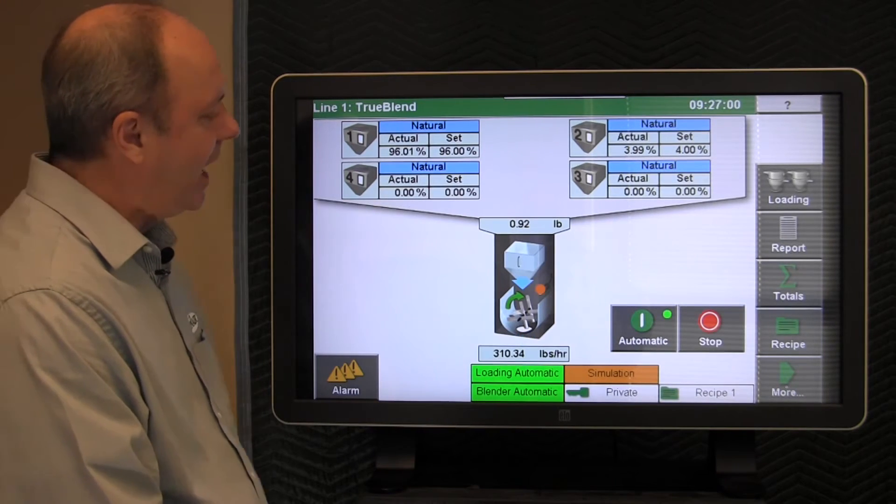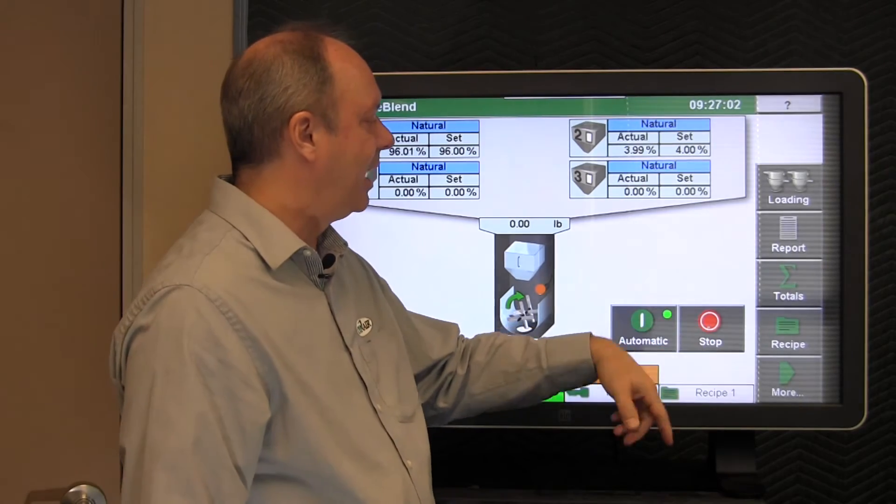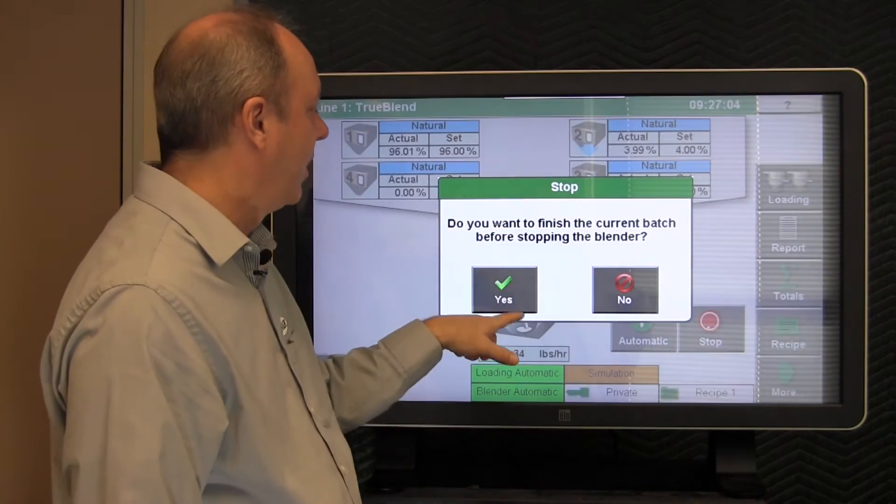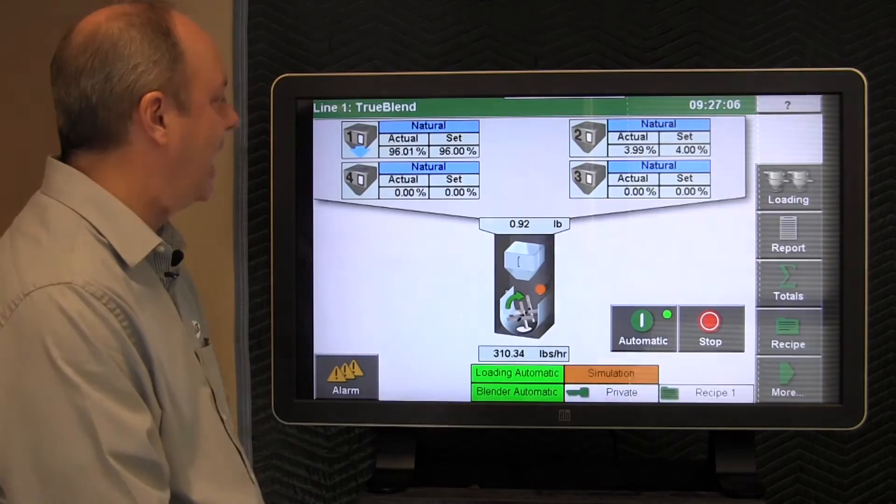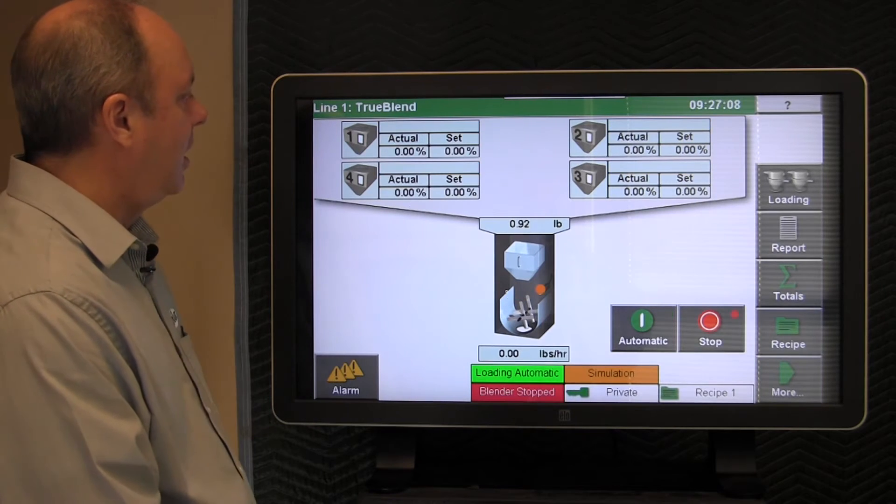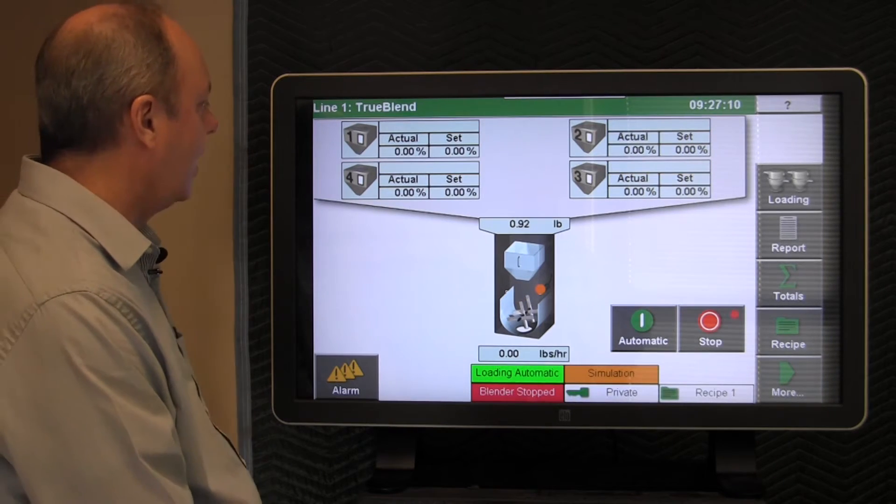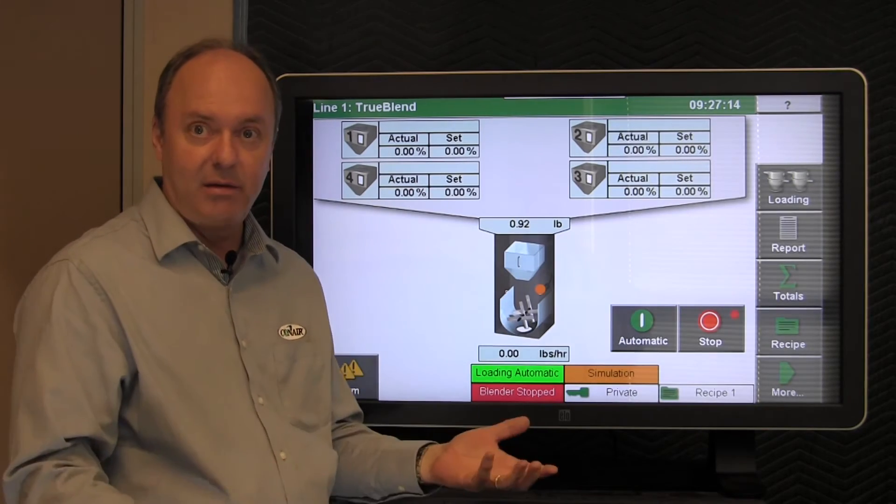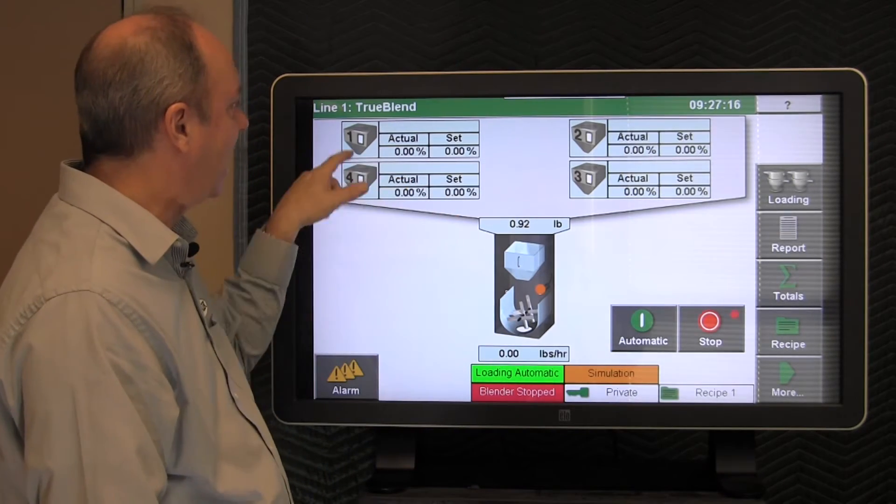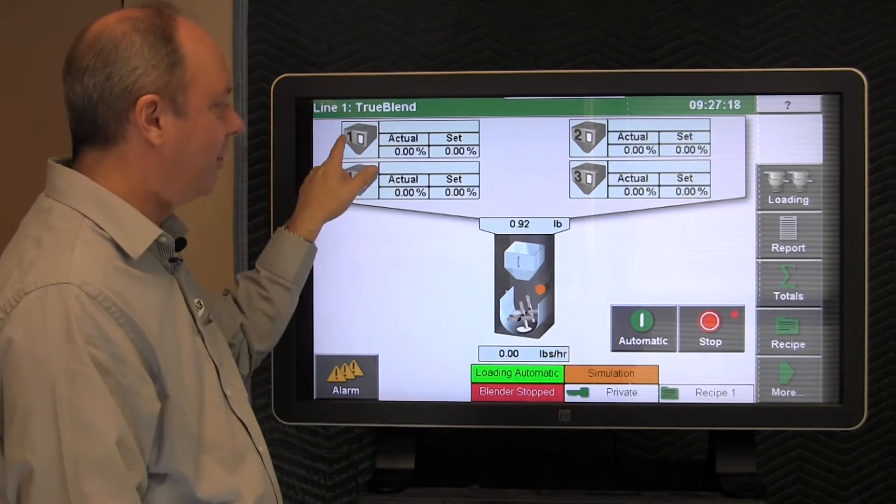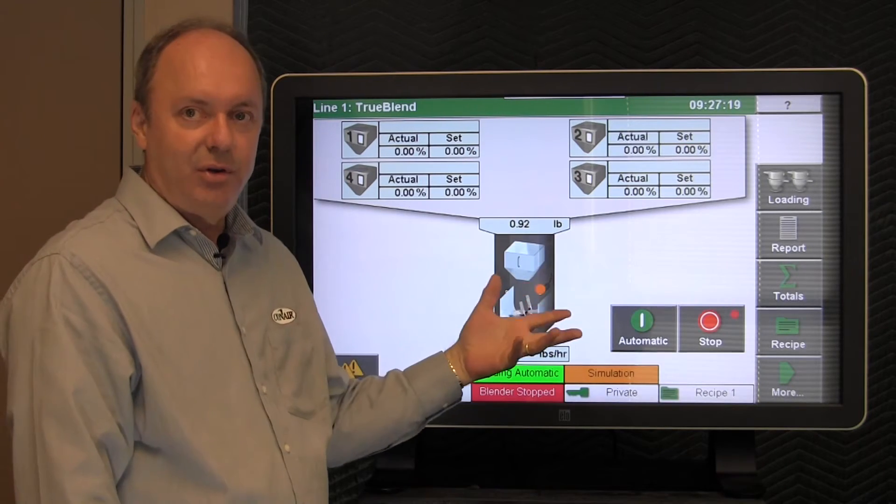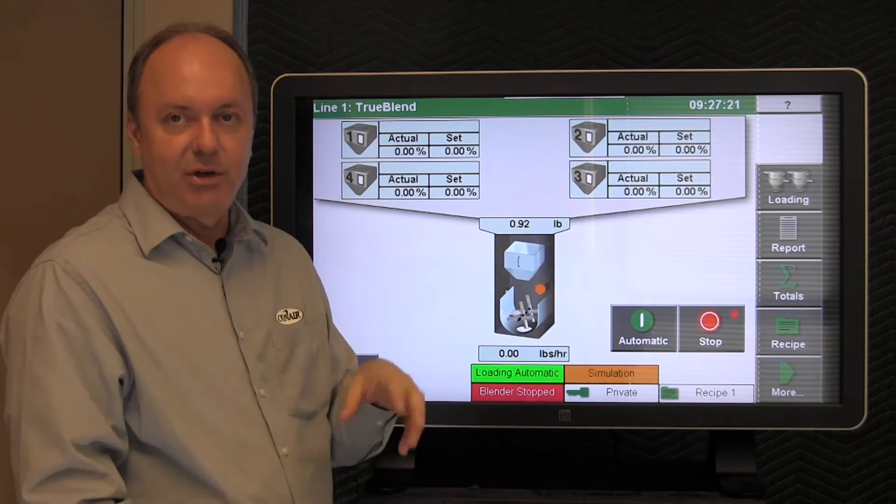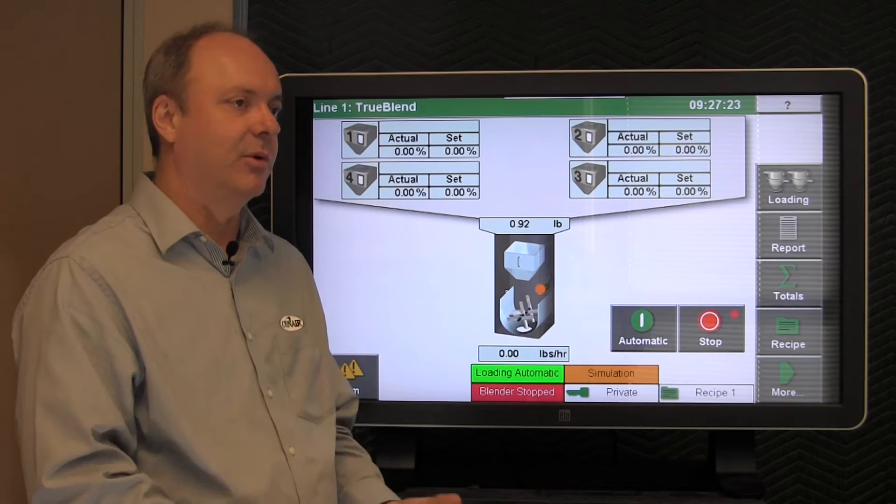In order to do that, it's advised that you actually stop the blender and we'll let it finish this current batch, and then it stops itself. At this point, you may want to drain the materials out because we're going to be actuating each of these component valves. And if you do that with material in them, then of course the material is going to come out.